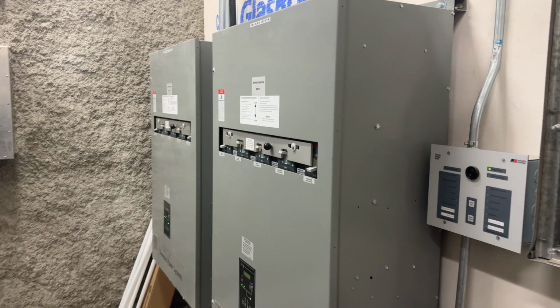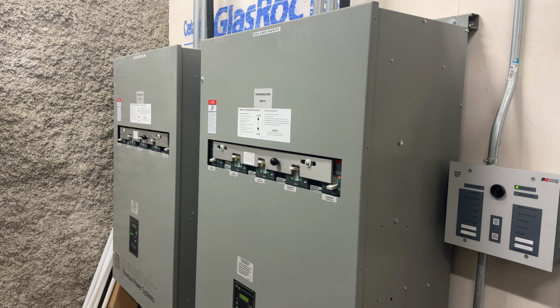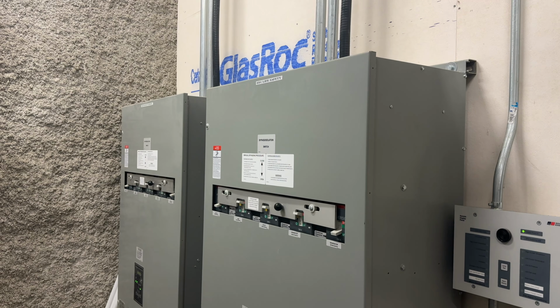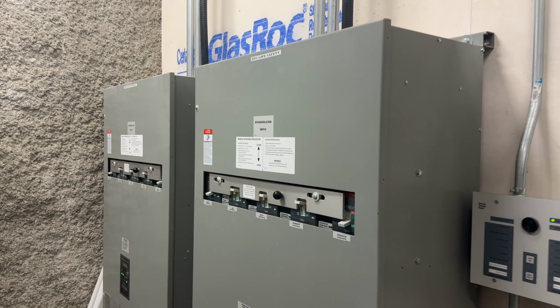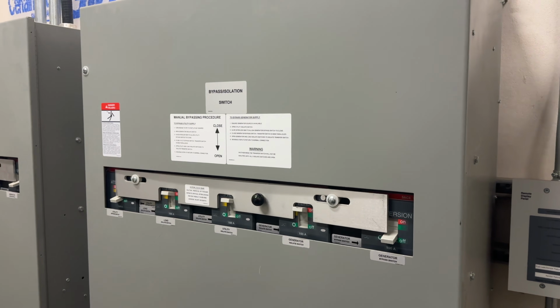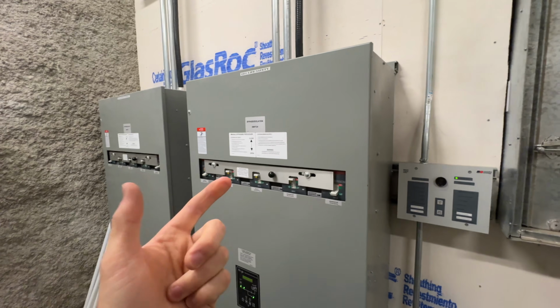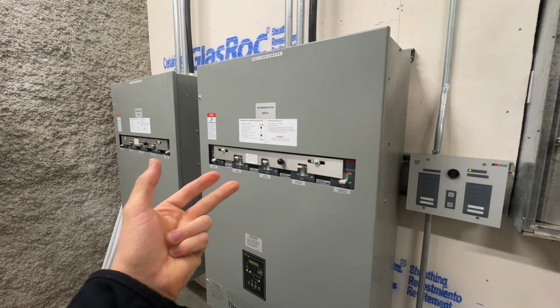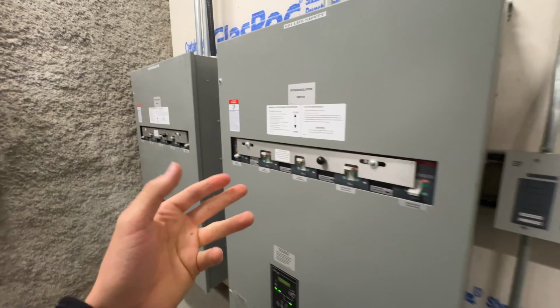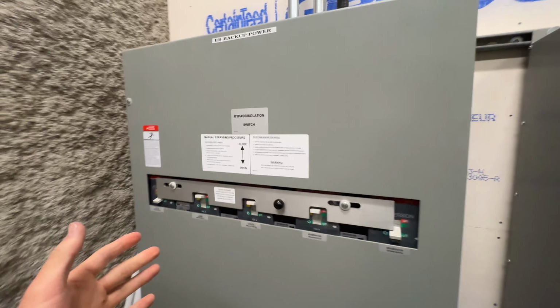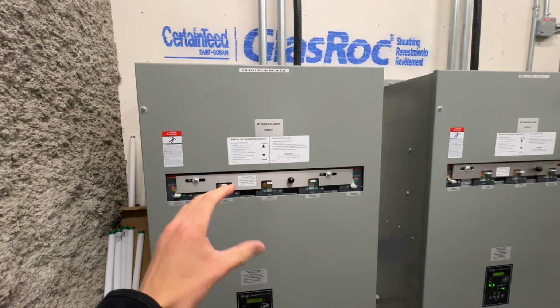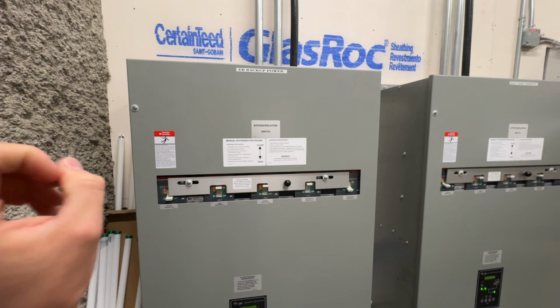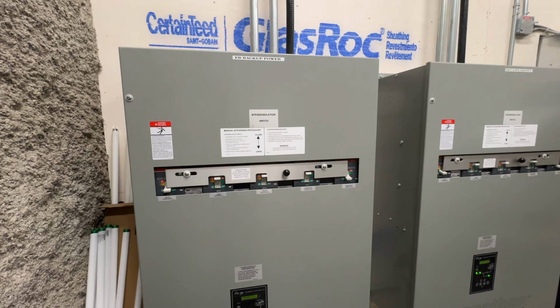All of the non-emergency lighting, everything that would be off in a power outage, won't go off in this test because we're not going to turn off the main breaker. We are going to be turning off two smaller breakers that feed both of our transfer switches. We have a life safety transfer switch and a general backup power transfer switch. Our life safety one powers, well, everything life safety. So your fire alarm, your smoke control, which is part of the fire alarm, and your emergency lighting, and I'm sure some other stuff I can't think of at the moment, but your general backup power powers things like your data racks to keep all of your data and communication going.